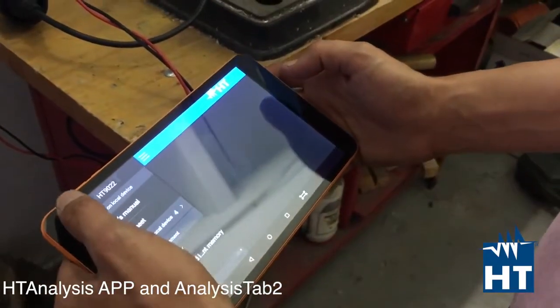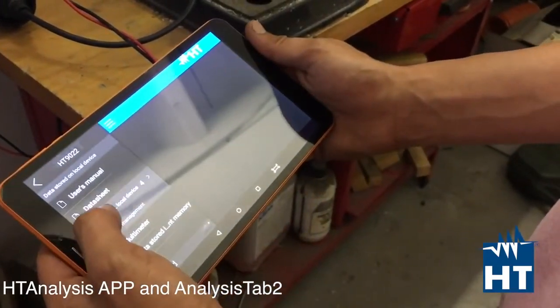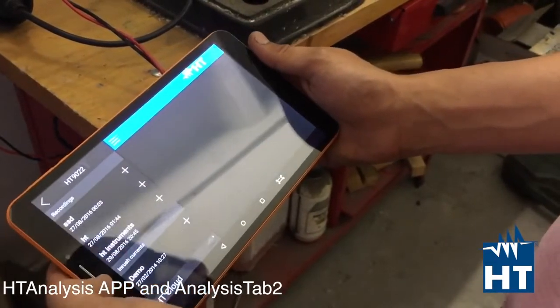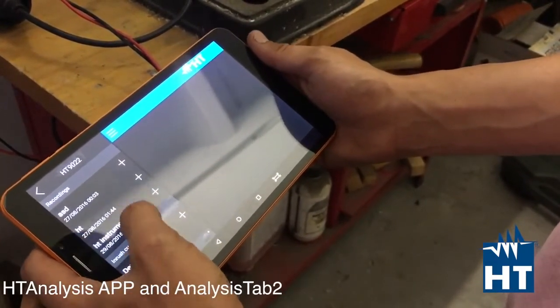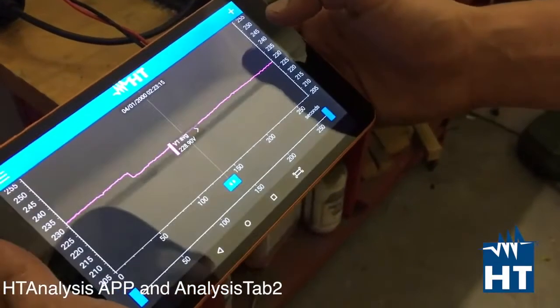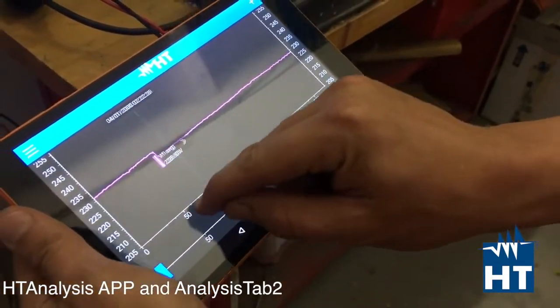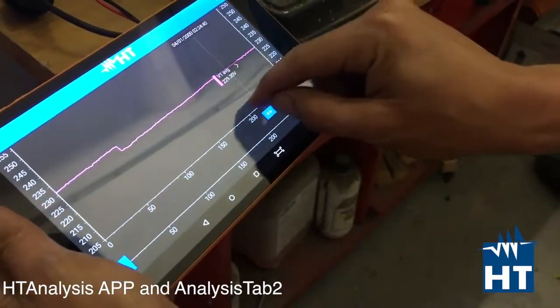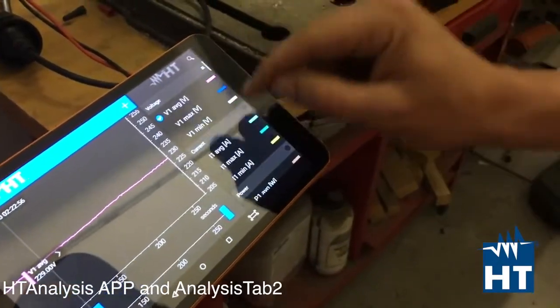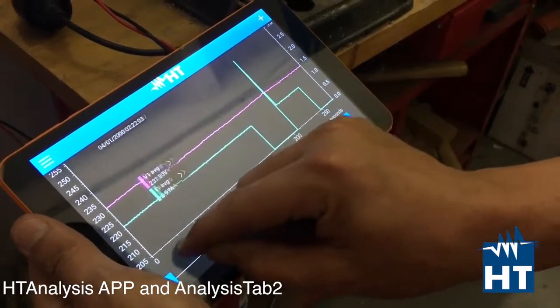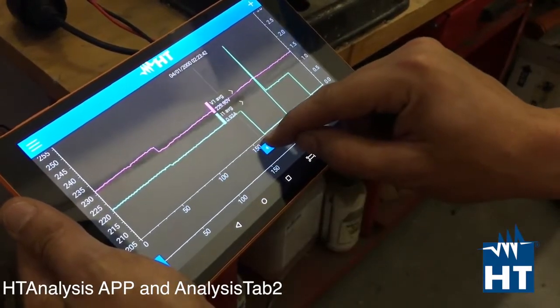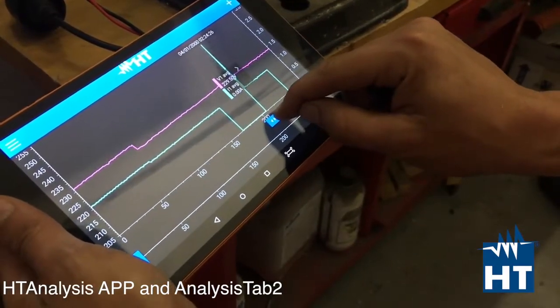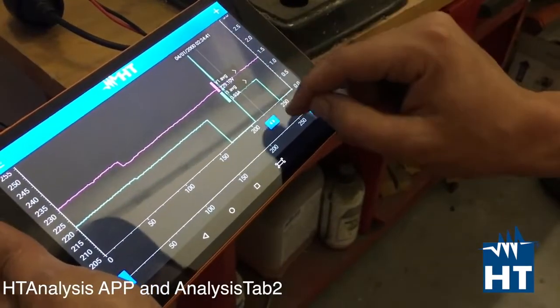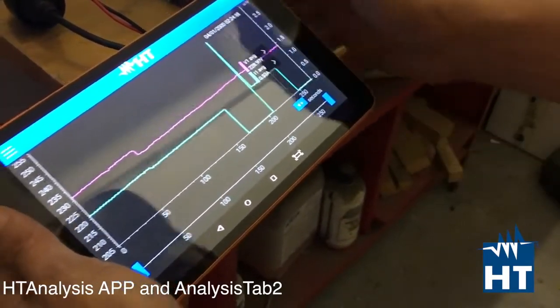Then go back to the menu, see data transferred on local device. We have the HT instrument, which is our data. We're going to open it. Now you're going to see the voltage. We can add even more parameters, the current for example. You see here is switch off, here is switch on again. So we got a little peak of current and I switched it off finally.